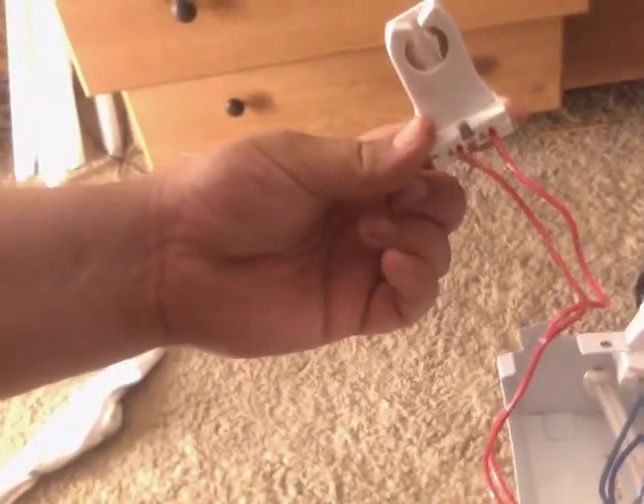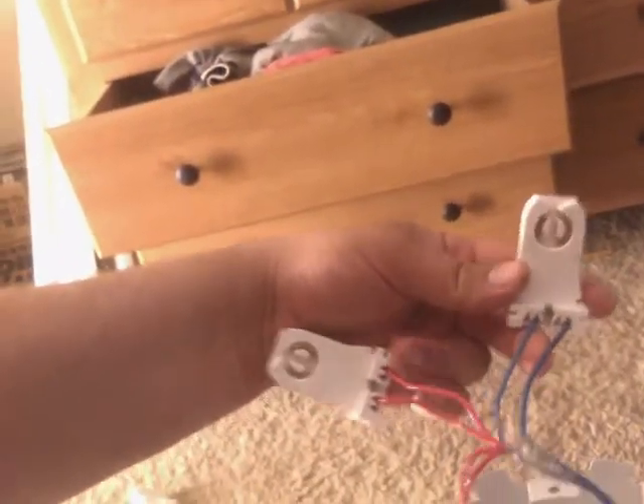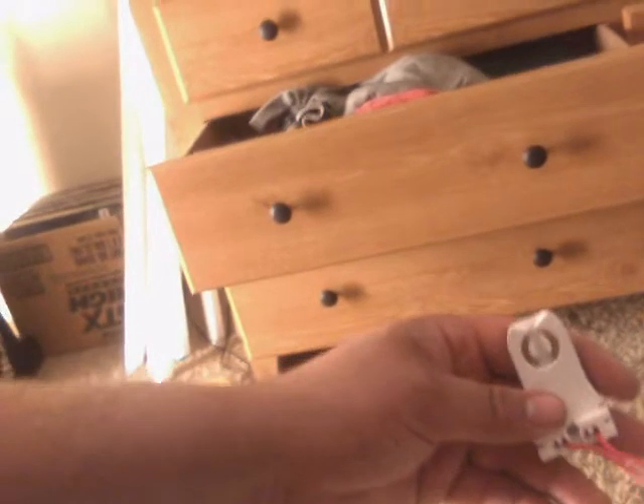On the red and blue wire side, both red wires go to one lamp holder, as shown. And both blue wires go to the other lamp holder. The reason there are two wires there is because that provides the filament heating voltage necessary to start the lamps.